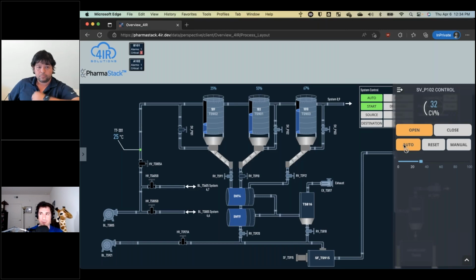I've never seen other software, SCADA software specifically, that enables you to perform electronic signatures like this using external identity providers, where Ignition itself doesn't have to have the username. A couple of years ago, I had a similar demo where we were using a local Active Directory installation over LDAP. Ignition communicates with Active Directory and passes those credentials. So when you're creating a form to collect that, you have to have a password field, and Ignition has to have those, which can be a potential security risk. In this case, because we're redirecting to the identity providers themselves, Ignition sees none of that. We're still able to capture a signature, which I think is pretty cool.